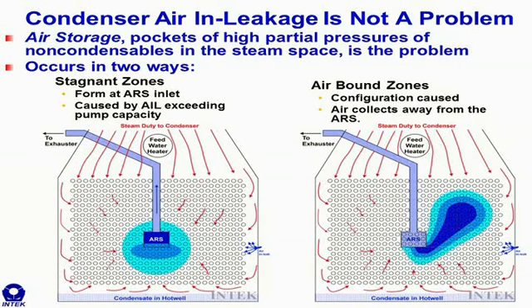The reason I say that condenser air in leakage is not a problem is that if the air can enter and exist in the condenser bundle without causing pockets of significant air partial pressures, then the condenser performance is not going to be affected. So the true root cause for all of the problems that people typically associate with air in leakage is really air storage. And that air storage can occur in 2 different ways. The first way is a stagnant zone. This is where that pocket of air collects and forms at the air removal section or the air cooling zone tube section. And it's caused by air in leakage exceeding the vacuum equipment capacity. And you can see that in the image on the lower right.